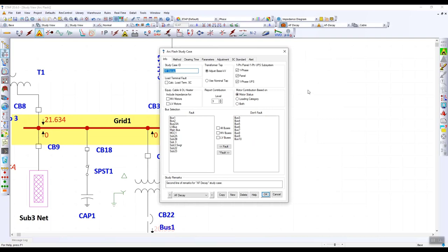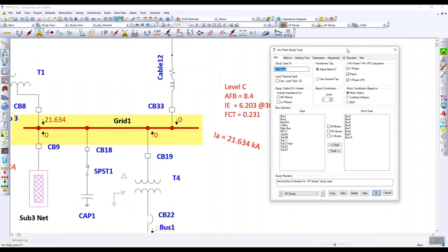Here I have opened up the study case. We can include additional options when running the arc flash study, like calculating the load terminal fault current for a motor, include impedances for medium voltage and low voltage motors. At the bottom, we can pick and choose which buses we'd like to fault all in one view rather than faulting each one individually on the single line.